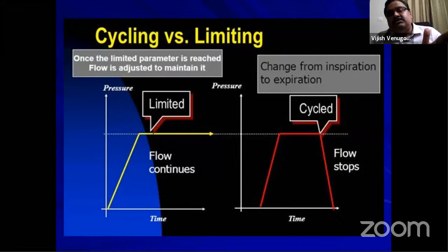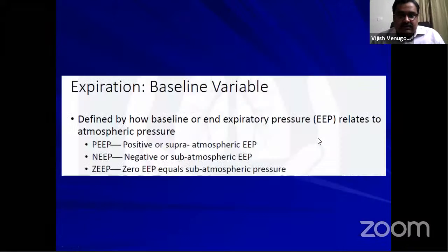Most of us would have a confusion about the difference between cycling and limiting. This is the difference. Once the limited parameter is reached, flow is adjusted to maintain it and flow continues. Whereas in cycling, there is an end of flow. The flow stops and there is a change from inspiration to expiration. Now that is regarding the 3 T's, and now coming to the baseline variable, that is expiration. So in expiration, you can modify the baseline variable. You can either give a positive end expiratory pressure, a negative end expiratory pressure, or a zero end expiratory pressure, which equals the atmospheric pressure.